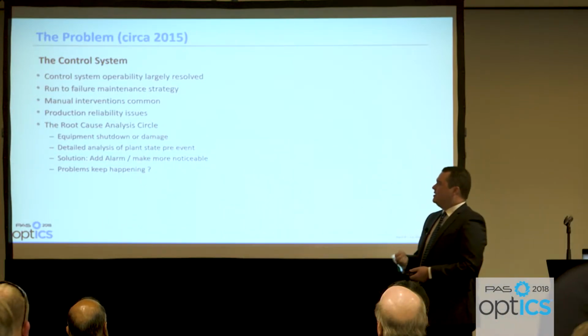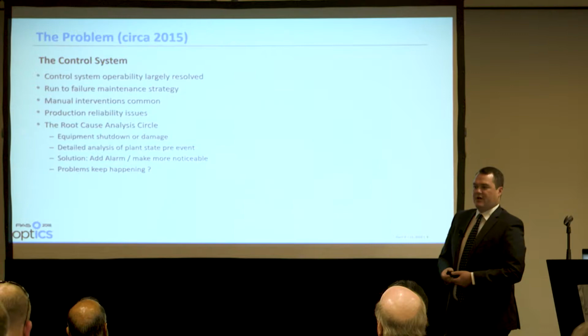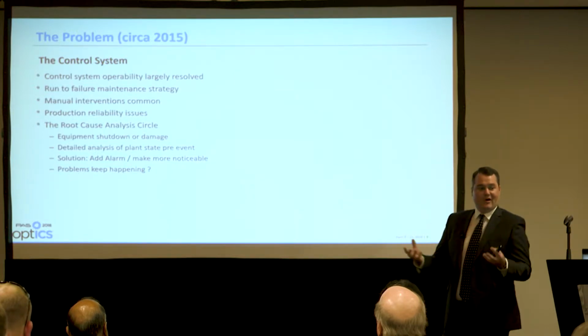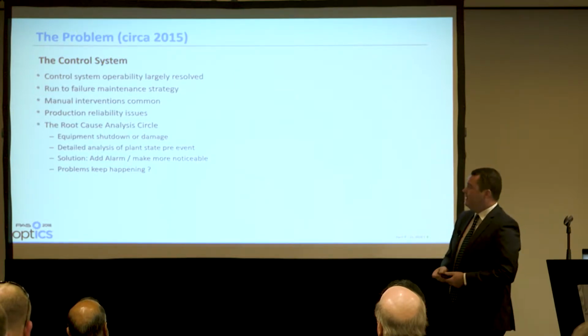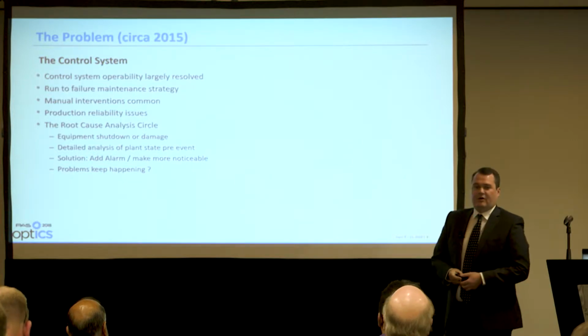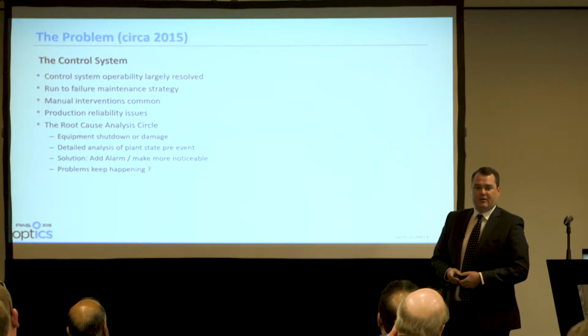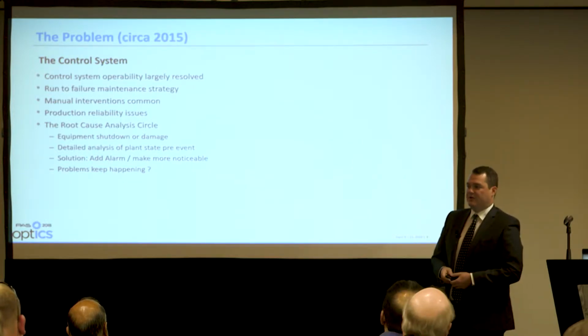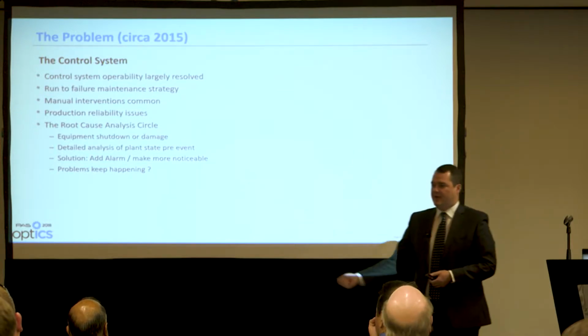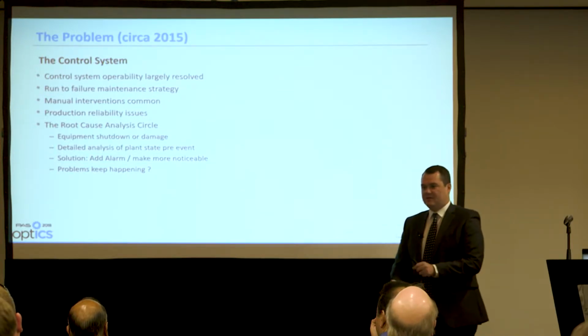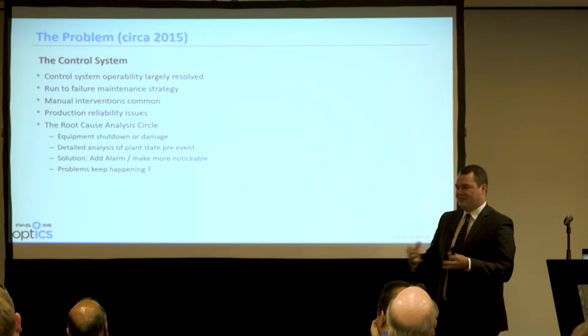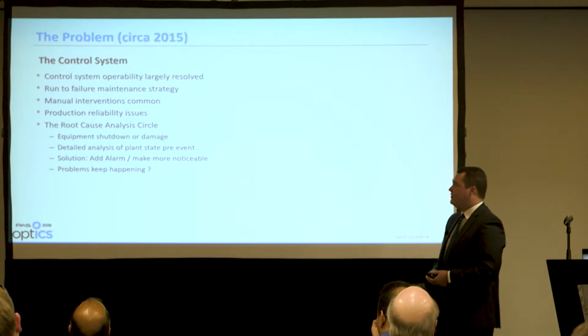But we're running a lot of the time in a run-to-failure maintenance strategy, driven by the high wear on the equipment, and manual interventions in the plant are common. It's really common that if you open and close a valve from the control system and it doesn't work, a guy goes down there with a hammer and hits it, or we bend things a bit, or chuck a hose in. That sort of thing is common and is an accepted way of running.